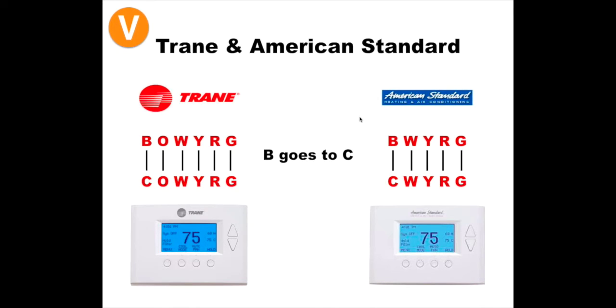Another thing to look for is a thermostat that has a B and an O wire connected at the same time. The rule with our thermostat, the CT100, is you'll never wire up a B and an O together. So if you see a thermostat with both B and O wired up at the same time, that should send up a red flag. Hopefully you remember you're never going to do both of those, and then you just have to figure out where the two terminals are going to go.